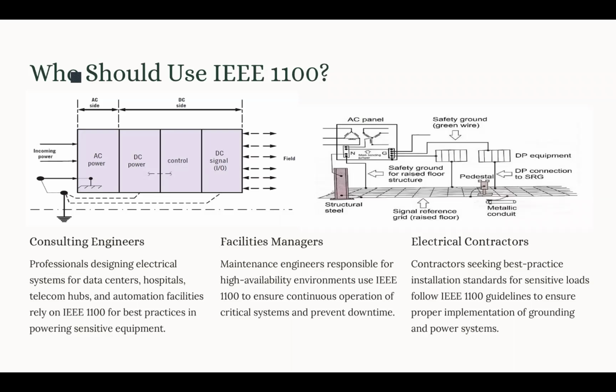Now, we could also use it in an industrial system, where consulting engineers use the standard to separate the zones of the system. We are going to talk about that. We have zone A, which is the sensitive electronics, and zone C, which is the motor drives. And this should be done with proper load segregation and filtering.